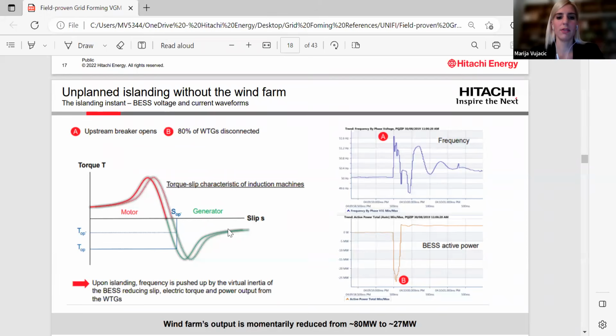At this moment, in this specific case, the wind farm didn't ride through this event, and this was due to a very tight over frequency protection at the wind farm. So BESS then started discharging and supplied the loads.